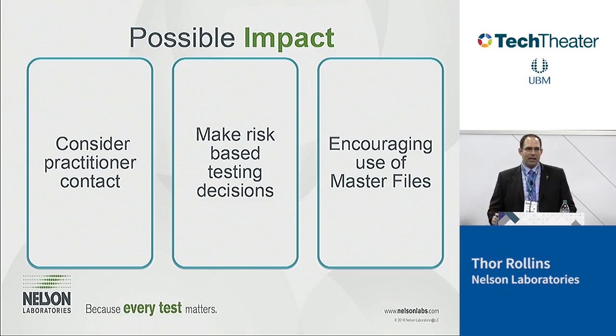But in the new guidance document, the FDA put in a section about practitioner use. Particularly, they said if they're not wearing protective clothing, so if your device is used without gloves or something like that, where the skin of the practitioner is going to contact the device, then we have to evaluate the risk to the practitioner, okay? Which is something new. We've not seen this from the FDA before. I have seen cases here and there, but never as a rule.